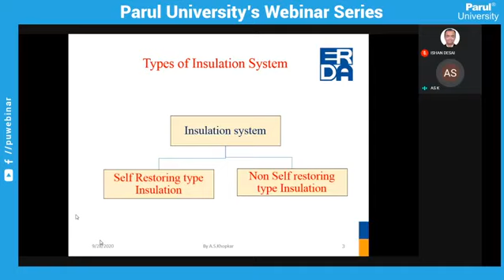It may lose the property completely or partially, but if such a material is there, then it is called non-self-restoring type insulation. The example of self-restoring type insulation is air or SF6 gas. Similarly, for non-self-restoring type, any solid material is an example, because after disruptive discharge it will lose its original property. So these are the differences between self-restoring type insulation and non-self-restoring type insulation, which are widely used while designing high voltage equipments.